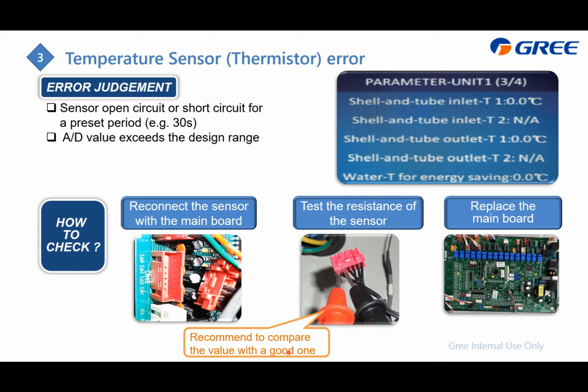And here is how we do it in China. When we do the troubleshooting, we always bring a good temperature sensor and just compare the resistance value of the good one with the suspicious one. If these two values do not change too much, that means the suspicious one is okay. And after that, if something is wrong with the main board, you need to replace it.